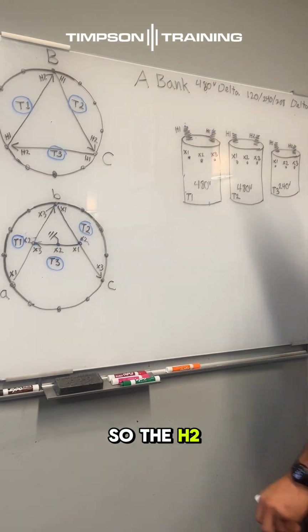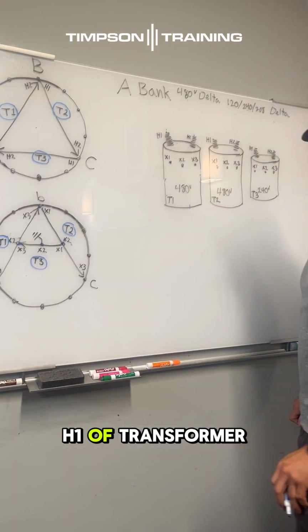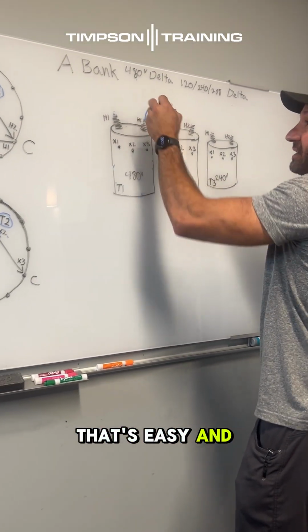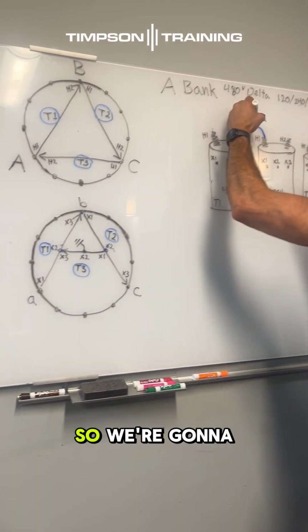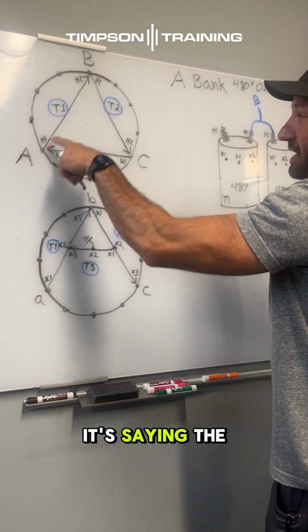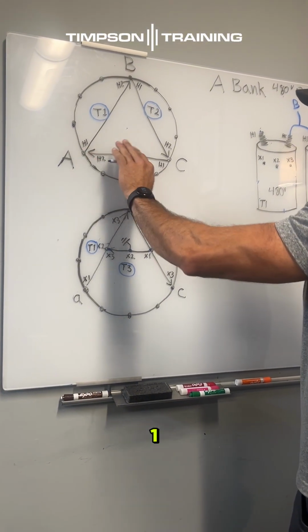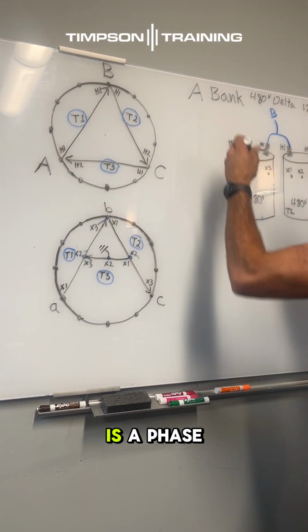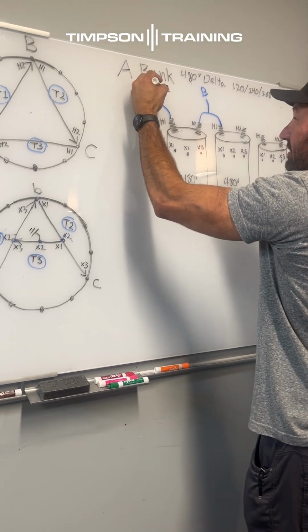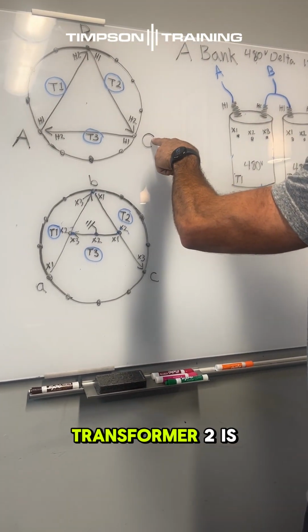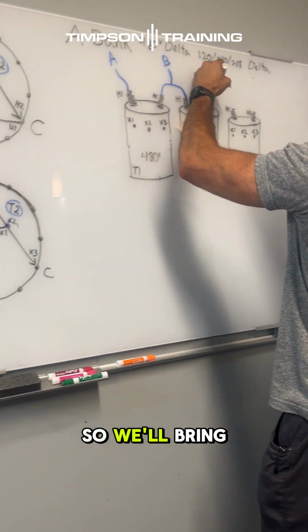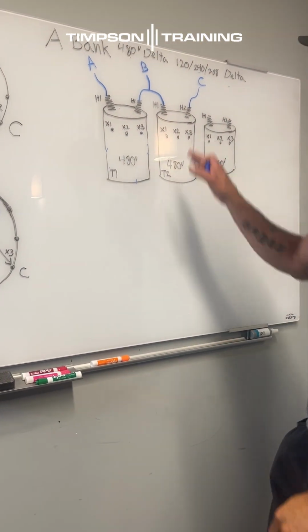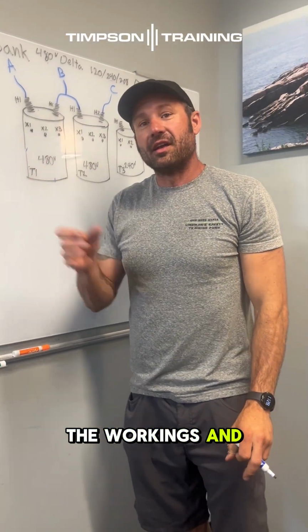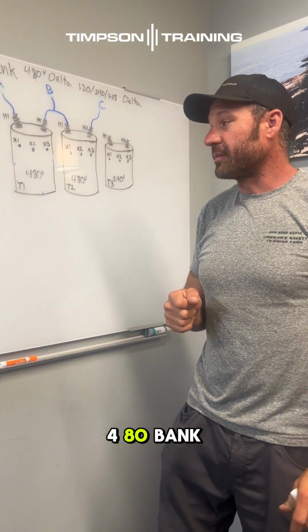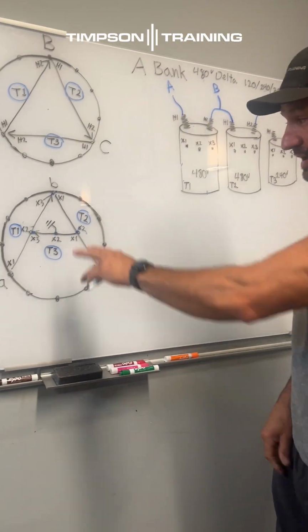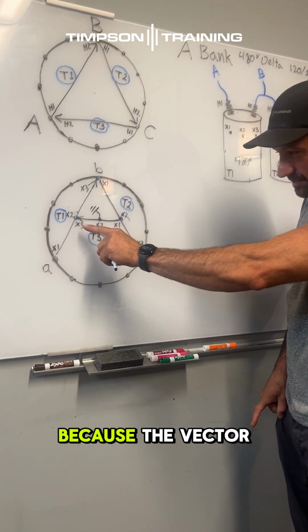So the H2 of transformer 1 ties to the H1 of transformer 2. That's easy, and it's telling us right there, that's B phase. So we're going to take that up, B phase. It's saying the H1 of transformer 1, remember, neglecting this, is A phase. So we'll make that A phase. And it's saying the H2 of transformer 2 is C phase. So we'll bring that up, make it C phase. Right now you have the workings and the tops of an open delta 480 bank. Now if we look at the bottom, you can see why they call it an A bank, because the vector looks like an A.